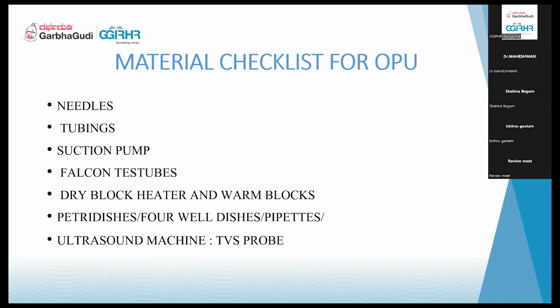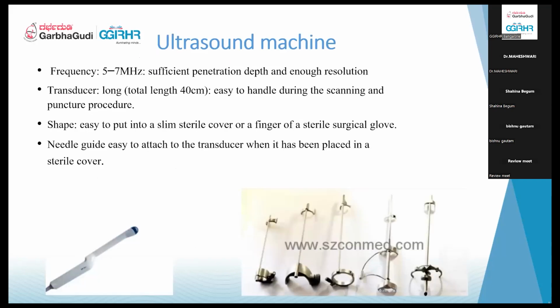And do you have a good ultrasound machine which has a transvaginal probe? We perform oocyte pickup using transvaginal probe only. So that also should be ready, and you should know what frequency the probe has. So these are the things that you should see for in the ultrasound machine, the frequency of the probe, so that the visualization will be better. So for a good visualization, you need to have a probe that has at least 5 to 7 megahertz, so that there is proper penetration of the signal, so that you will be able to see the area of focus, that is the ovaries and the surrounding structures, especially where there are vessels, especially the iliac vessels, are clearly visualized. So therefore, you need to have a good resolution probe.